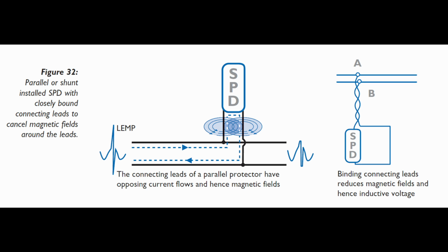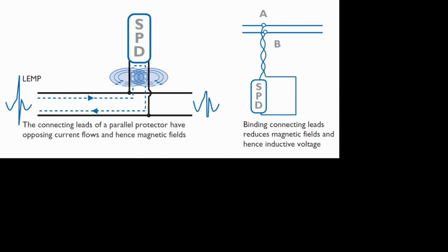Now there is another possible option which is not in the wiring regulations, it's in another publication. A link to that is in the description of this video, and it actually shows twisting the conductors together if your surge protector device is in a separate thing with just the 3 conductors going to it. Now the idea of that is that by twisting them together you're going to reduce the inductive effect of that, but the problem is that if you twist wires together you're going to have to make them longer, because as you twist them they obviously need more space to contain themselves. So just by doing that you'll already increase the length even more, so not really a valid choice. And ultimately if it's that far away anyhow there's something wrong with the design of it, so you might want to rethink where you're installing it or locating it.